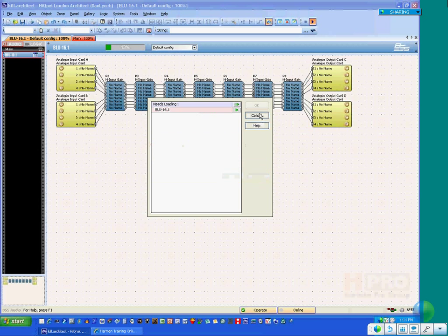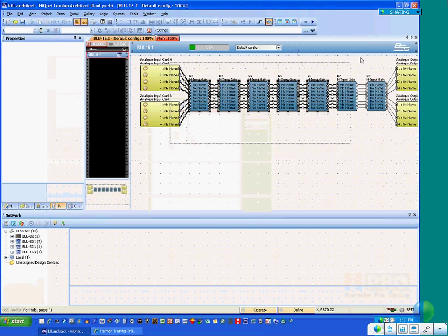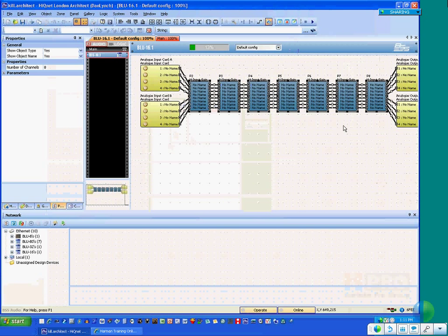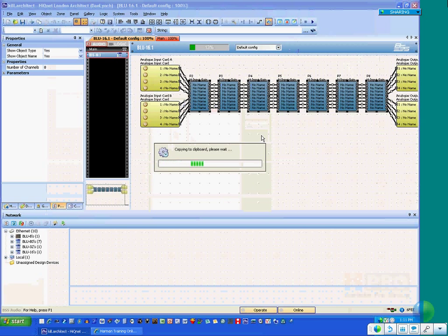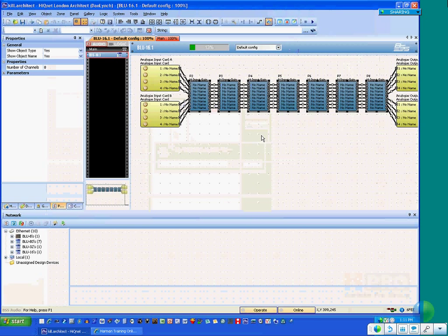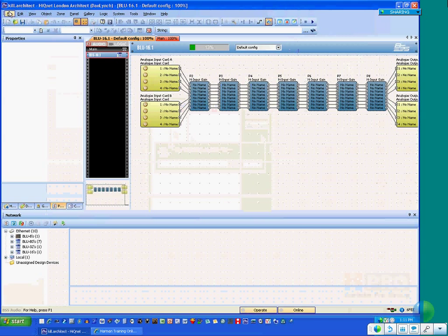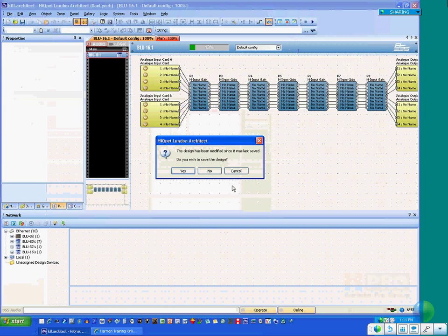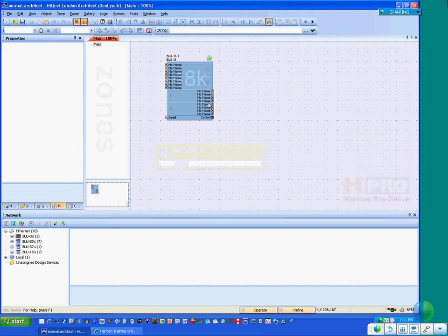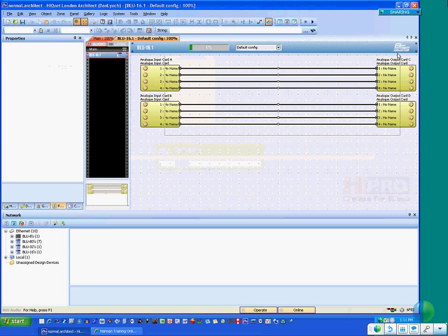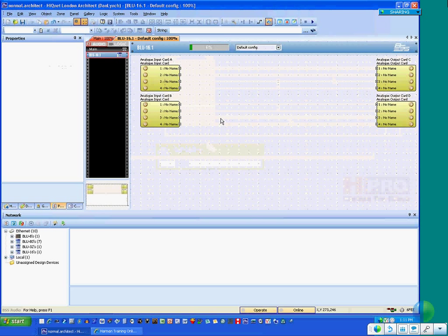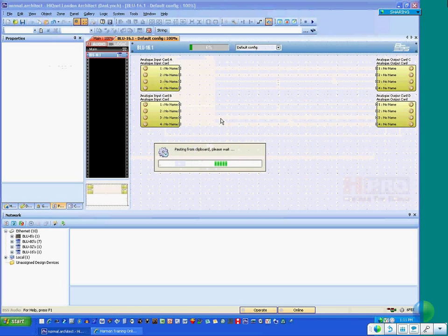If you're going to use box security, you must use design file security. Because if you don't, you just wasted your time. If you use box security but don't use design file security, then all that malicious person has to do is take your design file that you're using every day, go in and delete whatever the original programming is, and paste in the malicious programming, or program in the malicious programming, whatever works.